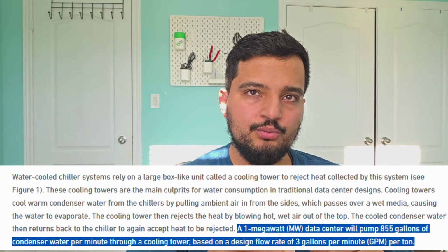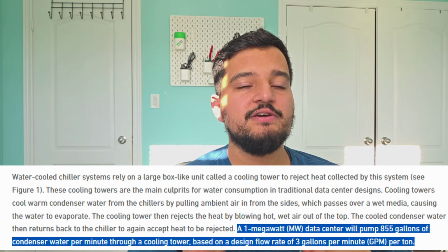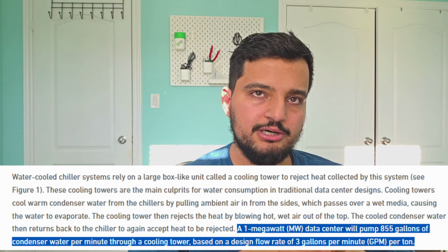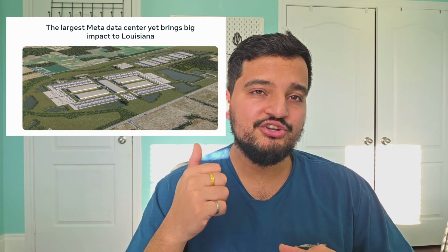According to the Uptime Institute, a 1 megawatt data center will pump 855 gallons of condenser water per minute through a cooling tower. Accounting for a 2% loss of water means that 17.1 gallons per minute of water is being used per megawatt. And that's just 1 megawatt. Companies like Meta operate data centers such as this one in Louisiana, which is over 2 gigawatts.